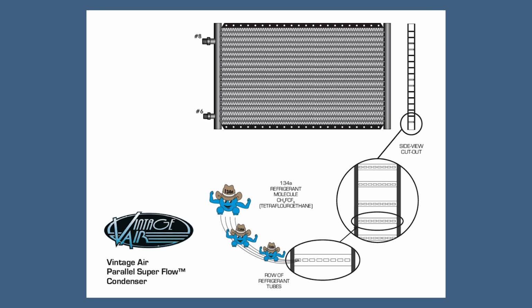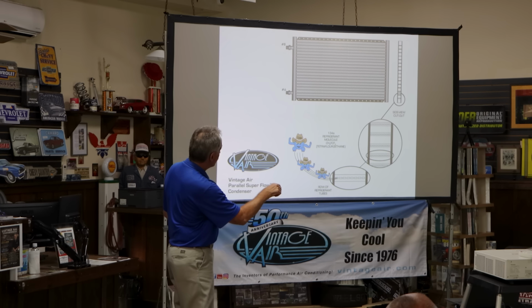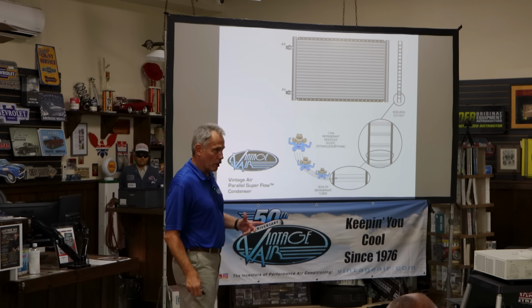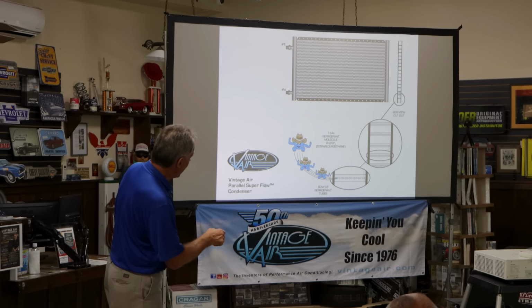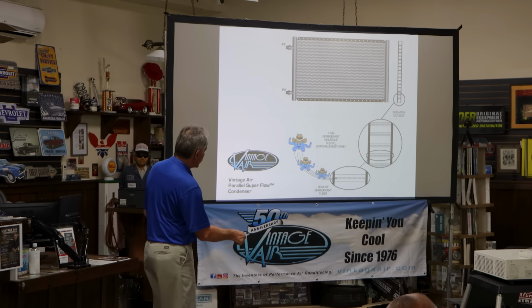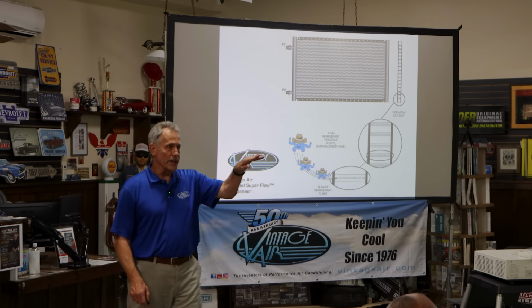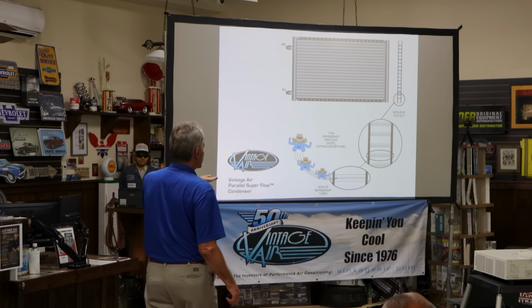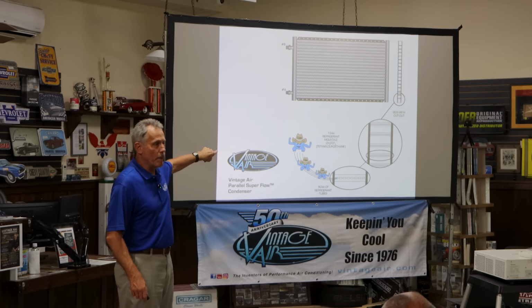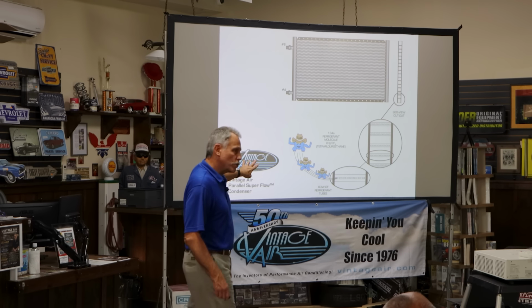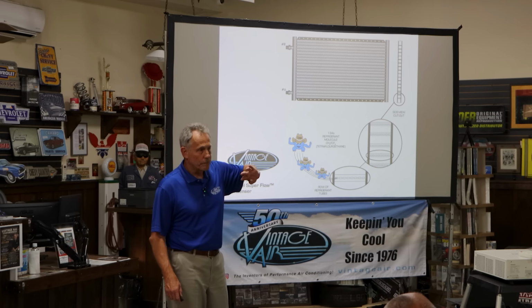The way a parallel flow works is your refrigerant comes in here, and there are dividers so that refrigerant goes across through these tubes, then drops down and comes back through these tubes in parallel - that's why it's called parallel flow. These tubes are separated into pathways, hallways, and by doing this you dramatically increase the surface area on your heat exchanger, which increases your heat transfer.